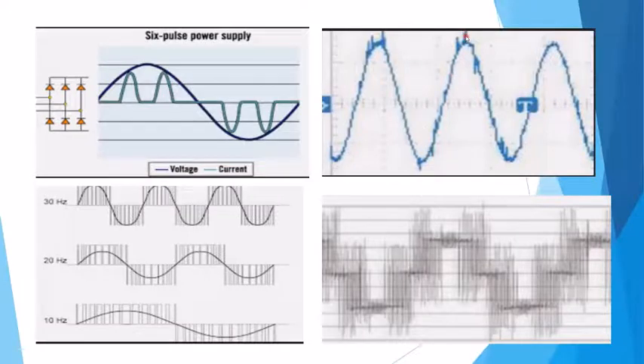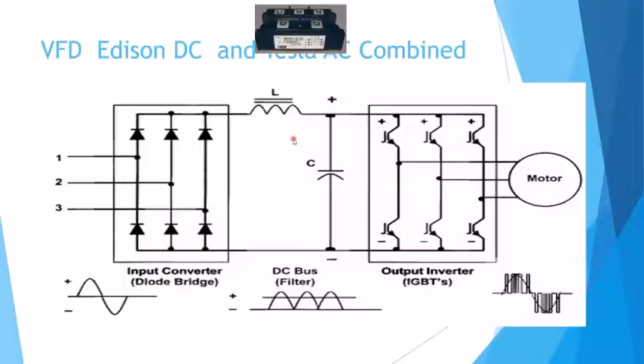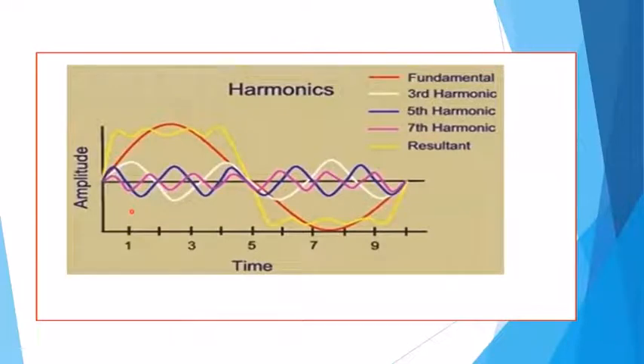It also is very critical that you look at the wire and the insulation coming in to the VFD control, because if this ends up getting too high over a period of time, so a lot of them have gone to shielded cable, they've gone to various ways to basically ground and get rid of that noise. And I'll go into what they call harmonic filters here fairly soon.